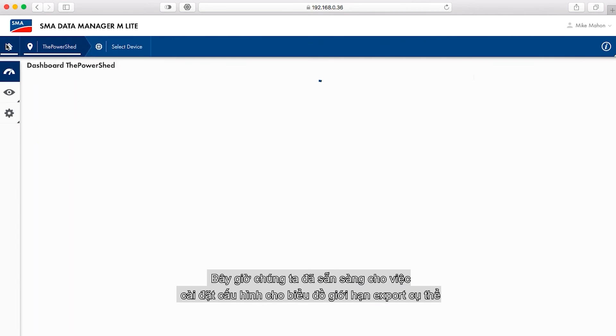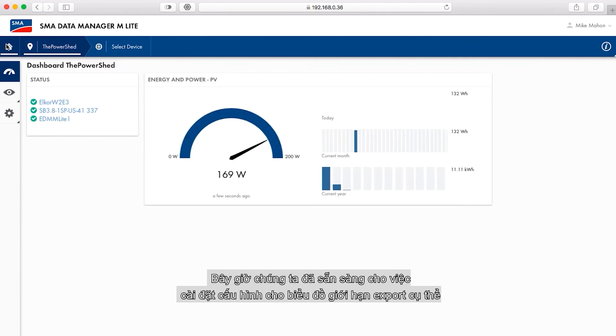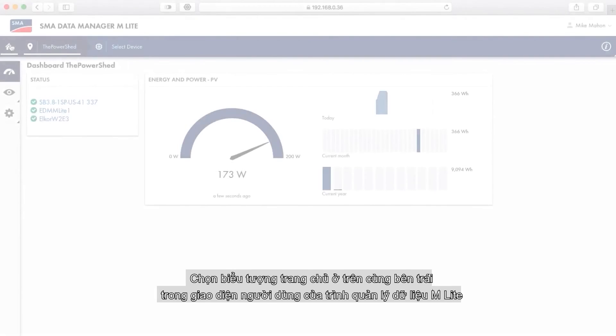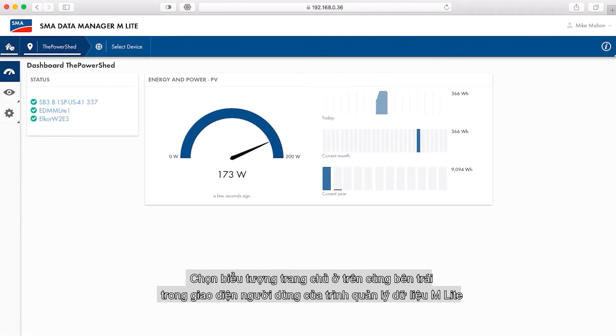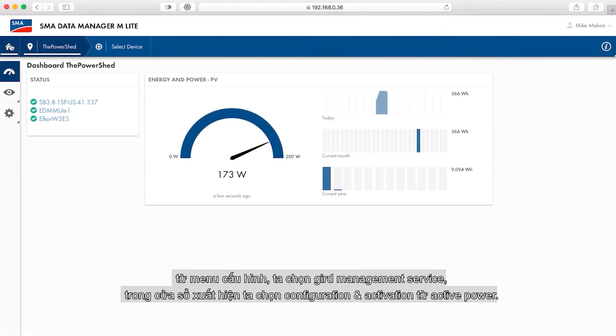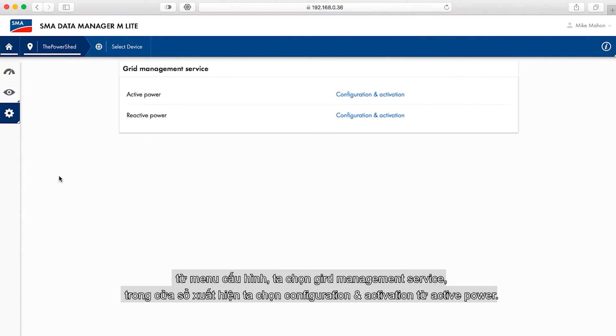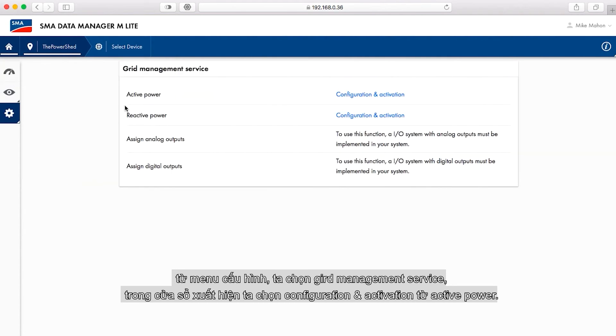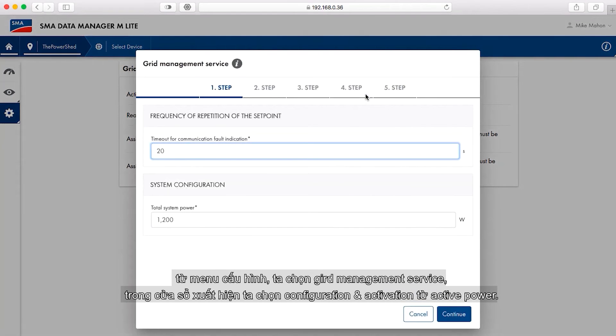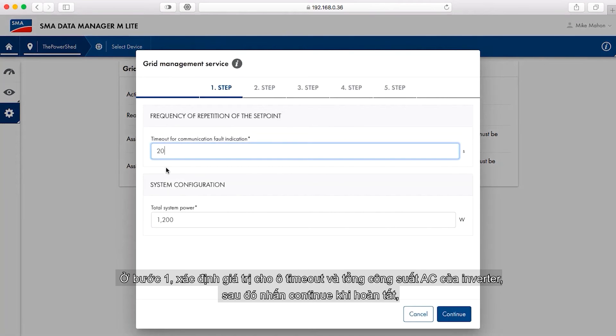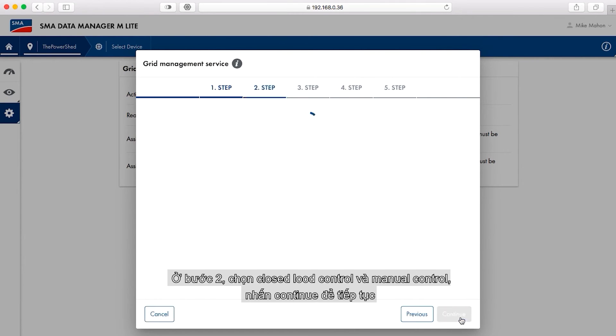Now we are ready to configure the settings for the specific export limitation scheme. Select the home icon at top left in the data manager MLite user interface. From the configuration menu, select grid management service. On the window that appears, select configuration and activation across from active power. In step one, set values for timeout and verify the total system inverter AC power. Select continue when done.